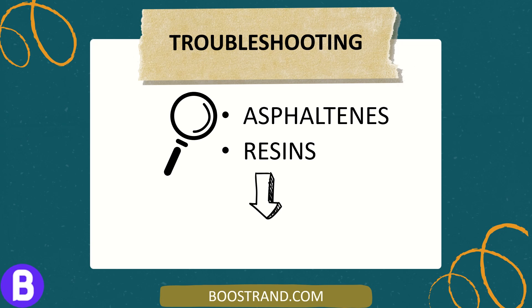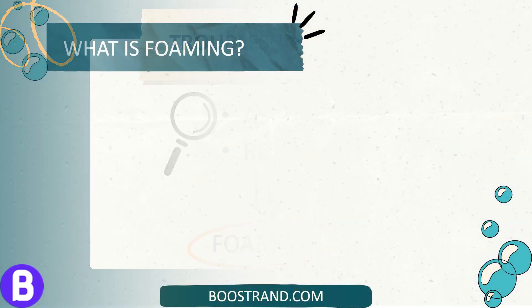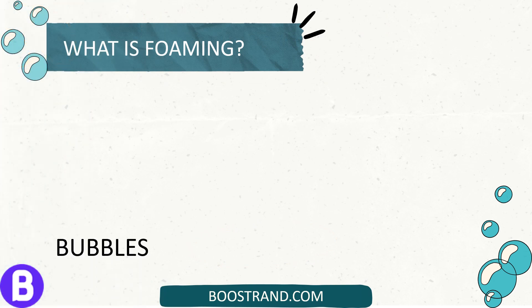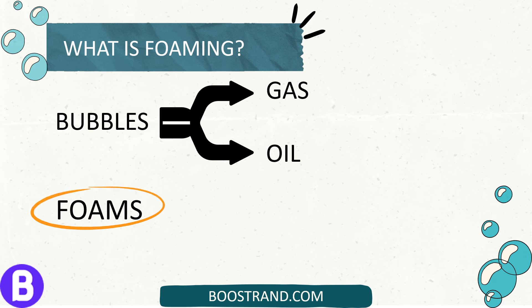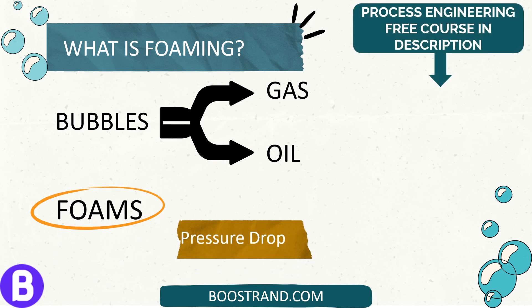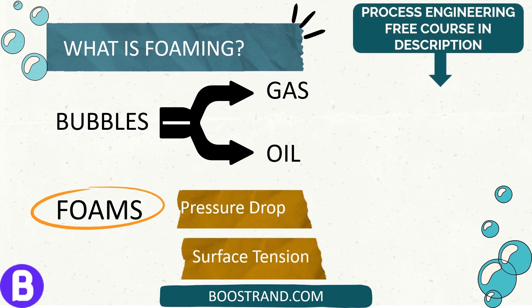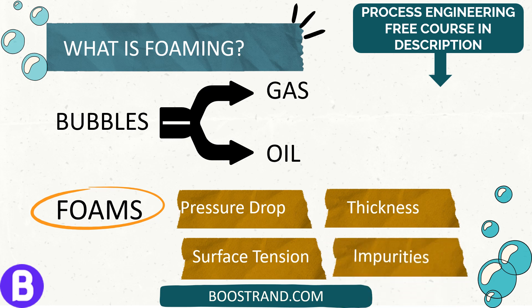The issue with these fluids is that they caused foaming inside the separator. Foam is like tiny bubbles of gas covered with a thin layer of oil. This makes it harder for the gas and oil to separate efficiently. Foam shows up where the gas and oil meet when the pressure in the separator drops, or because of things like surface tension, thickness of the liquid, and impurities in the oil.